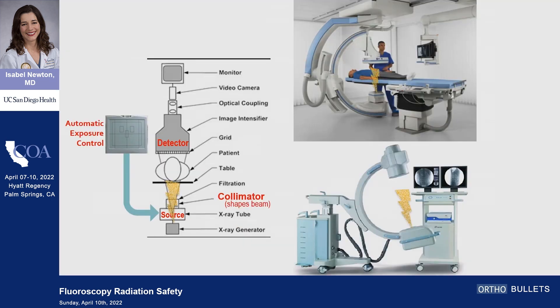Let's first do the anatomy of the C-arm. The source is where the x-rays come from, the photons come from, and they pass through the patient and are received at the detector in a differential pattern which creates your image. There's this thing called the automatic exposure control, which is like a feedback mechanism that says: I've received enough photons, I'm going to shut it off.